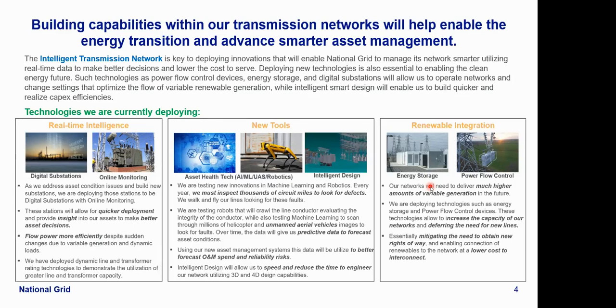However, from a system reliability perspective and thermal violations, storage is going to have limited capability or limited applications compared to distribution, because on the transmission side, the basic rule for planning is contingencies can happen anytime and can last for a long time. So if you're designing energy storage to solve an overload issue on a transmission line due to contingency, that energy storage needs to be able to continue mitigating that overload for a long time.